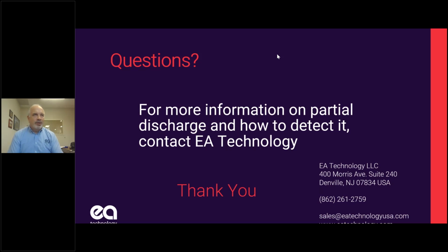Well, offline tests are beneficial for a variety of reasons. You can vary the voltage level up and down. You can do it above line voltage, you can do it below line voltage, you can find out where the PD starts, where the PD stops. You do have to be careful when you re-energize the cable. If you ever use XLPE and DC high pot or DC testing, you can end up with cable failures, but that typically doesn't happen with modern VLF equipment. Yeah, offline is a great test.